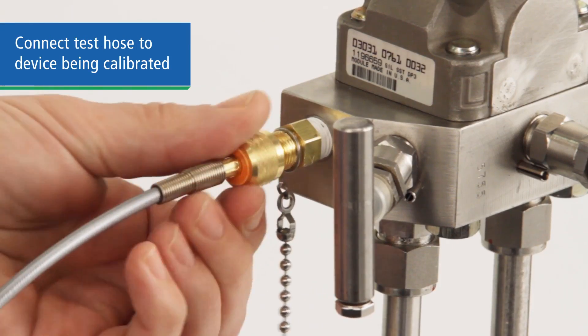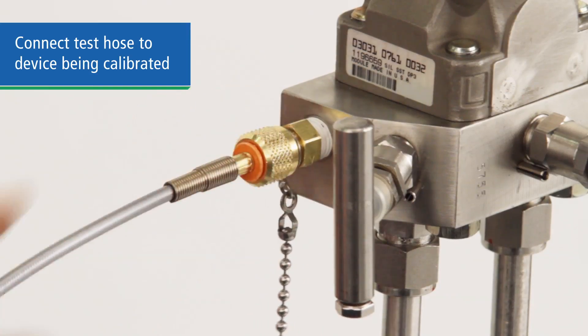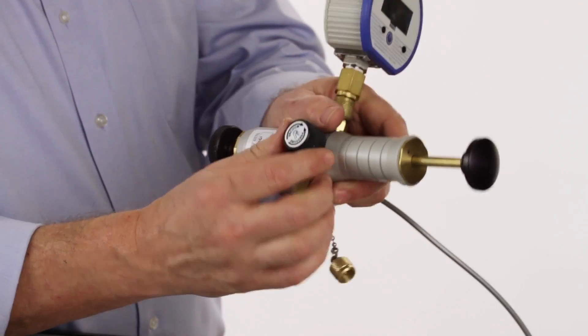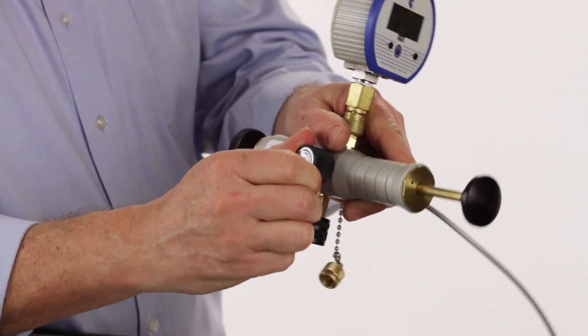Connect the other end of the hose to the device being calibrated. Make sure the vernier adjustment is near the middle of travel. Then close the bleed valve tightly. The spool valve on the side of the pump switches the action from pressure to vacuum, depending on your need.